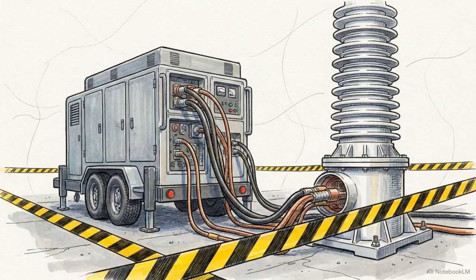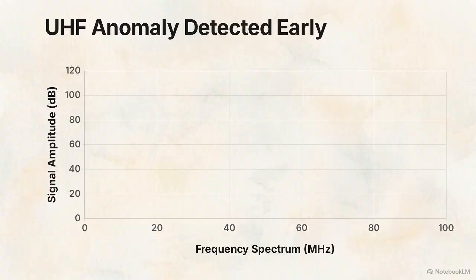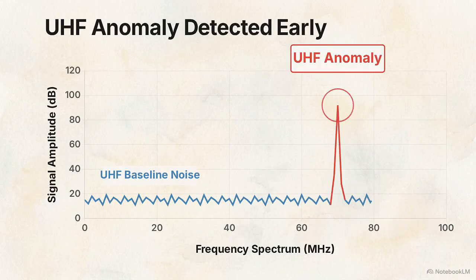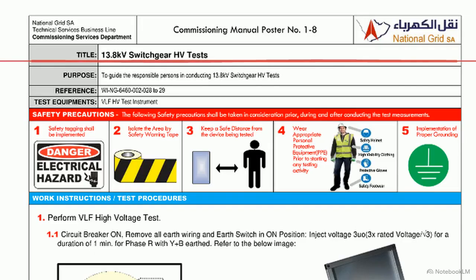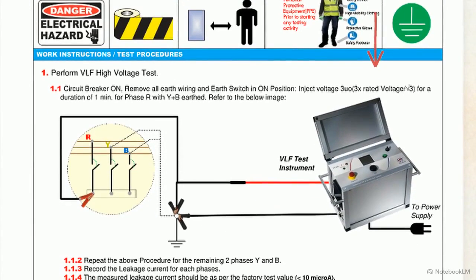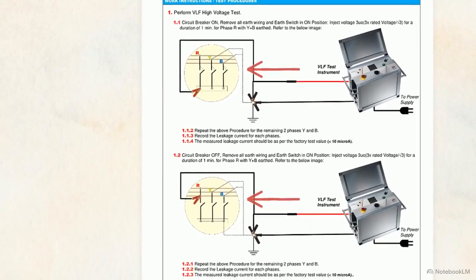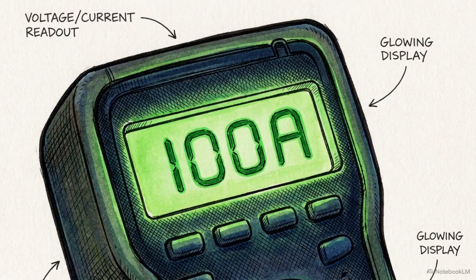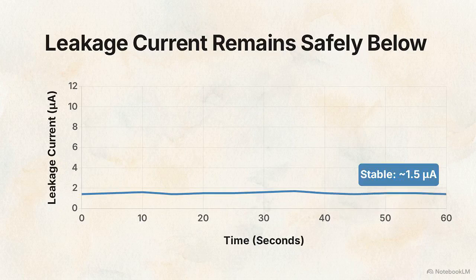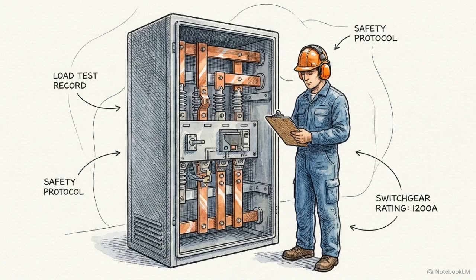The final physical stress tests push the equipment to its operational voltage limits using very low-frequency injection, while monitoring for microscopic flaws using UHF partial-discharge detection. This diagram illustrates the VLF high-voltage test procedure on 13.8 kV switchgear. A potential of 3 times the rated operating voltage is applied, with the circuit breaker in both the on and off positions. During the high-voltage injection, leakage current must remain below limits, without any flashovers or abnormal acoustic noise.